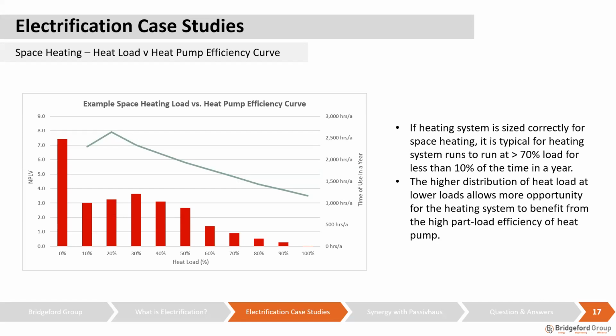Your curve reflects a truly oversized heat pump, which may well happen in a passive scenario, where it's able to cycle down to a low point, but invariably it will switch off. And then it will start back up again. And I'm just wondering if that's reflected in that curve that you presented. Short cycling only happens if, like I mentioned earlier, you majorly oversize a system, then that system can keep short cycling within this area. And if you undersize the system, you'll just keep topping out over the 100% load. And so you just have to rely on buffer storage tanks to even enable your system to work. Sorry, did I answer your question? I may not be getting the question entirely correct.